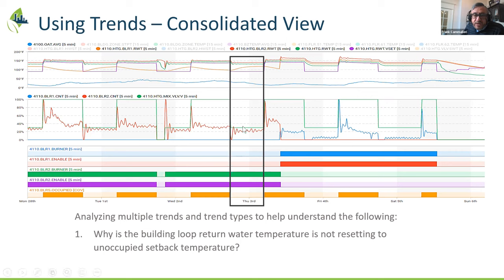The answer really is this, and this is a real life example: this mixing valve has a minimum position, it's set for 30% here, and this is with one boiler operating.